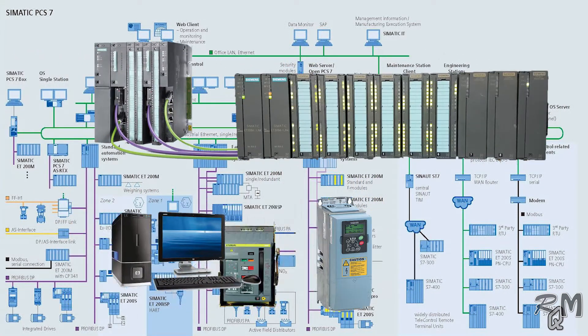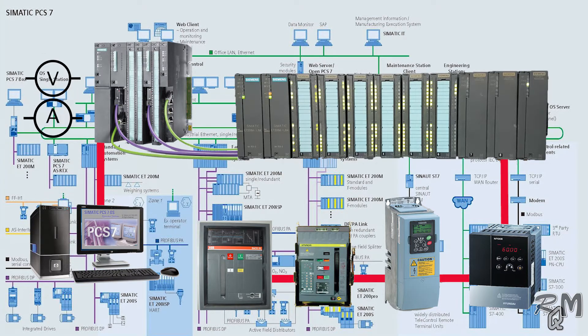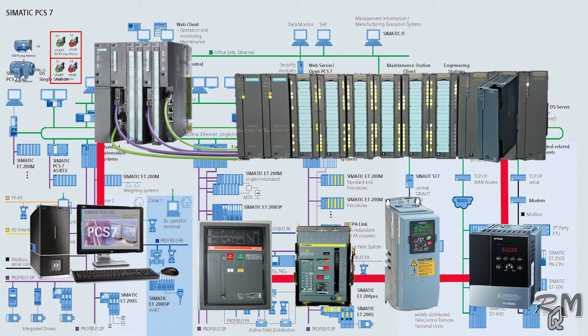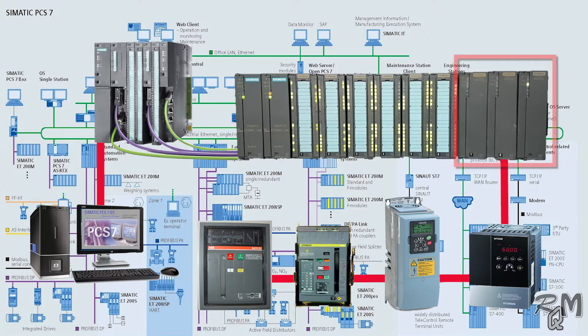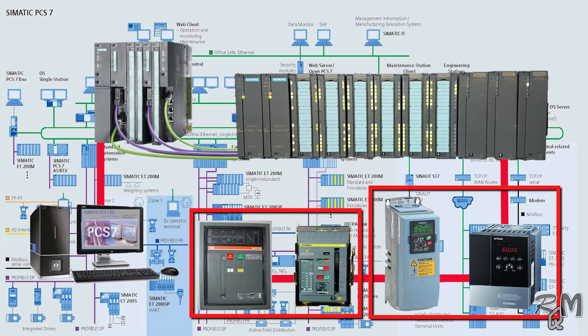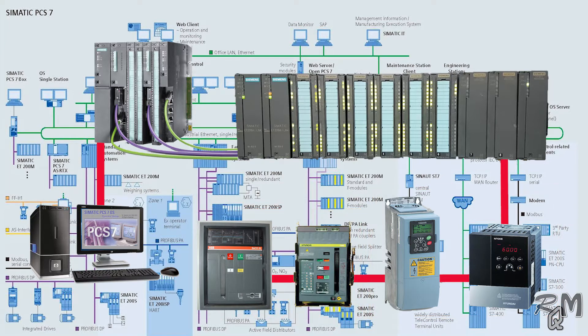In my case, we are using CP341 in Siemens SIMATIC PCS7 to receive and transmit data to different variable frequency drives, low voltage breakers, and medium voltage breakers. PCS7 receives data of different parameters like frequency, current, voltage, and status of devices through the CP341 communication module. Sometimes PCS7 is unable to update parameters exchanged through CP341, and all related parameters of variable frequency drives and breakers become frozen, so the desk operator of PCS7 is unable to get the real status of these devices. This happens due to communication failure of the CP341 module.